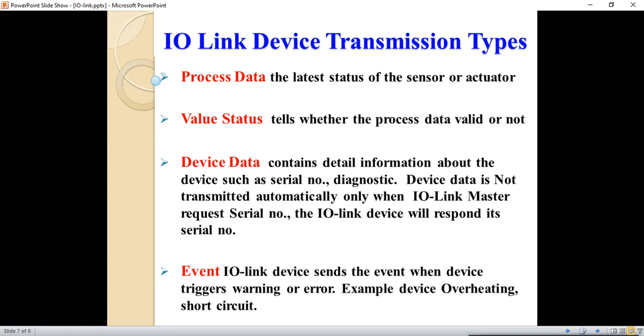IO-Link device transmission types: the first is process data, which means the latest status of the sensor or actuator. The second type is value status, which tells whether the process data is valid or not. The third is device data, which contains detailed information about the device such as serial number and diagnostics — this is not transmitted automatically but only when the IO-Link master requests it. The fourth type is the event, where the IO-Link device sends an event when it triggers a warning or error, such as device overheating or short circuit.